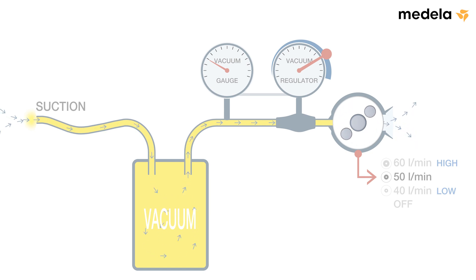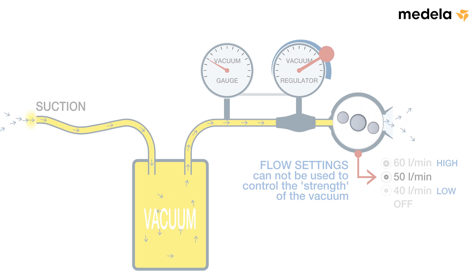It is important to note, the flow settings cannot be used to control the strength of the vacuum. This is the job of the vacuum regulator.